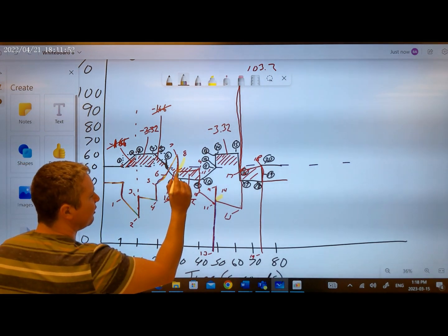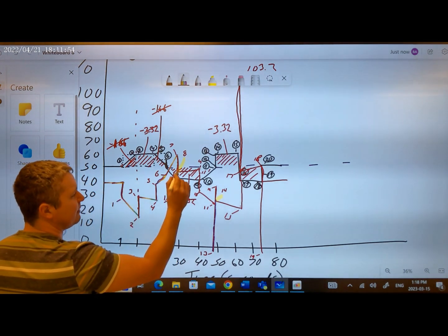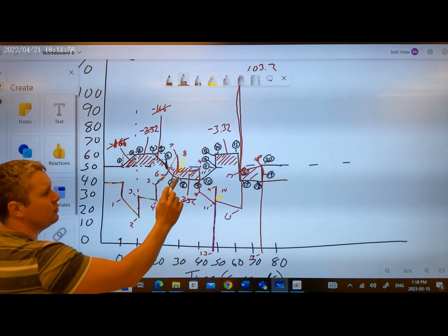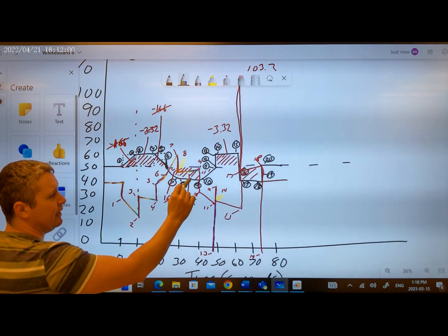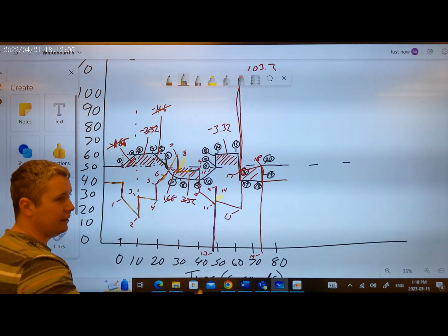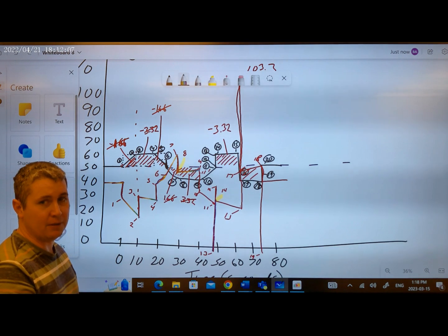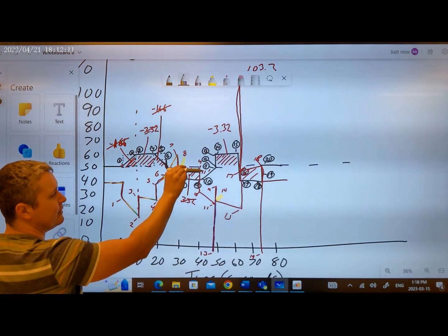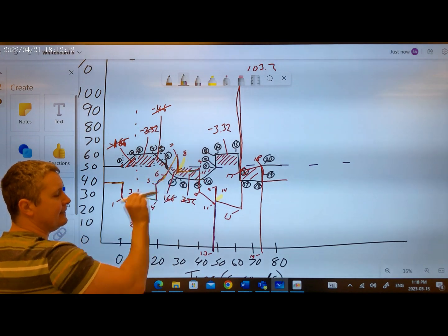So now we went from, I think, 45 up to 48, due to the fact that all this accumulation of negative error now makes our controller want to output a more positive number, trying to make the process variable come back to the set point.